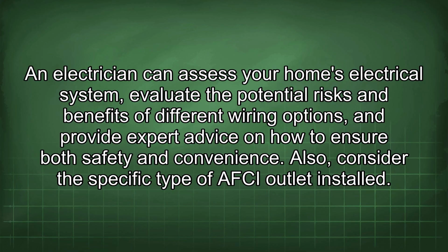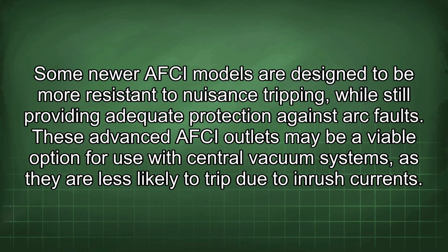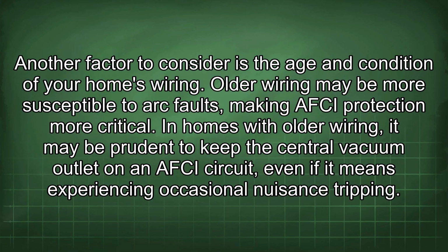Also, consider the specific type of AFCI outlet installed. Some newer AFCI models are designed to be more resistant to nuisance tripping while still providing adequate protection against arc faults. These advanced AFCI outlets may be a viable option for use with central vacuum systems, as they are less likely to trip due to inrush currents. Another factor to consider is the age and condition of your home's wiring. Older wiring may be more susceptible to arc faults, making AFCI protection more critical. In homes with older wiring, it may be prudent to keep the central vacuum outlet on an AFCI circuit, even if it means experiencing occasional nuisance tripping.